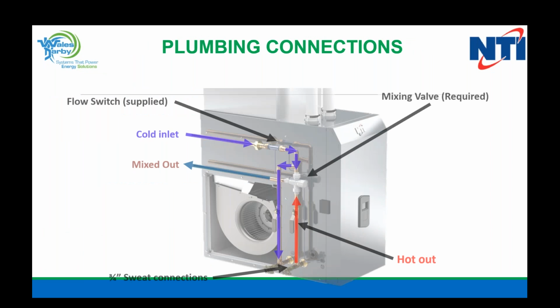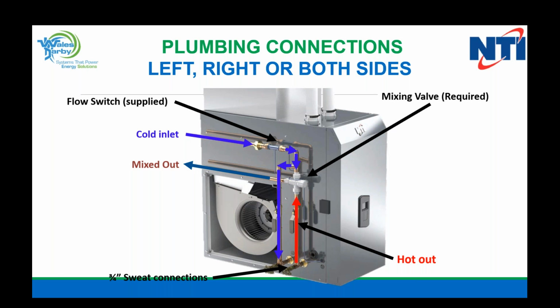Okay, so it's highly recommended, and we really don't want to see it any other way, to have a mix valve. The reason behind the mix valve is we need to make sure that we can support the hot water that the house needs and support the hot water that the coil needs to support the BTU within the home. So this can be piped right or left.